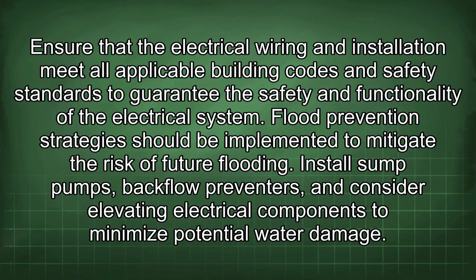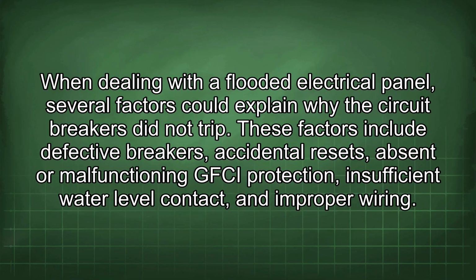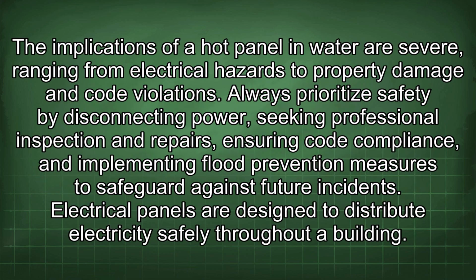Flood prevention strategies should be implemented to mitigate the risk of future flooding. Install sump pumps, backflow preventers, and consider elevating electrical components to minimize potential water damage. When dealing with a flooded electrical panel, several factors could explain why the circuit breakers did not trip. These factors include defective breakers, accidental resets, absent or malfunctioning GFCI protection, insufficient water level contact, and improper wiring. The implications of a hot panel in water are severe, ranging from electrical hazards to property damage and code violations.